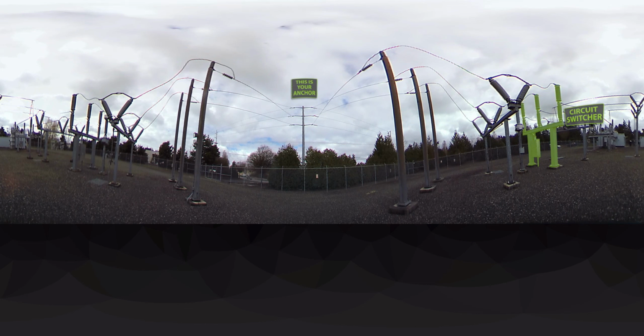This breaker is here to isolate the substation in case of a fault or other mishap. In the case of a fault, SF6 gas would be shot into the top insulators, and much like blowing out a match, this SF6 gas fills the space between the two contacts, blowing out the connection, breaking the flow of electric current, and thus breaking the circuit.